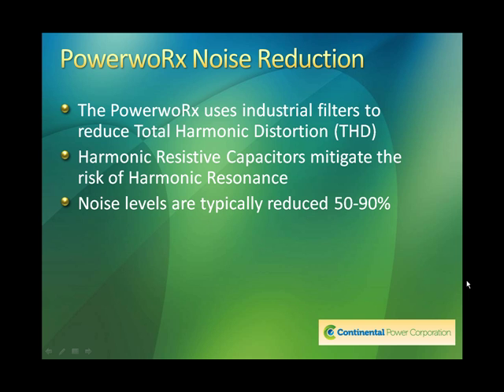PowerWorx uses industrial filters to reduce total harmonic distortion. As I mentioned, harmonic resistive capacitors mitigate the risk of harmonic resonance. And noise levels can typically be reduced anywhere from 50 to 90%. So a facility we're working on right now has a large computer center used for the entire corporation. They have multiple buildings on the property, but in this particular building, all the computers and all the power supplies that are driving the computer equipment, the drives and all the peripherals that go with it, generate huge amounts of noise. Lots of current on the neutral, total harmonic distortion between 3 and 4%. We're able to put our units in there and reduce that distortion, give cleaner power for those computers to run on, and solve a real world problem for this particular company.